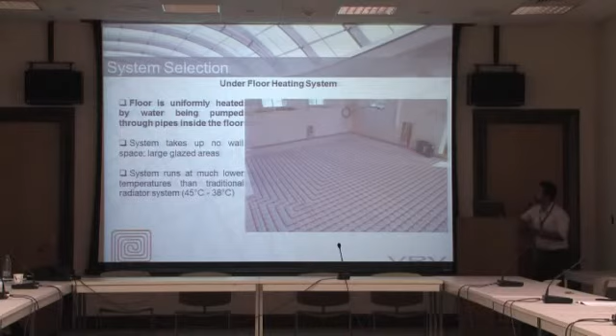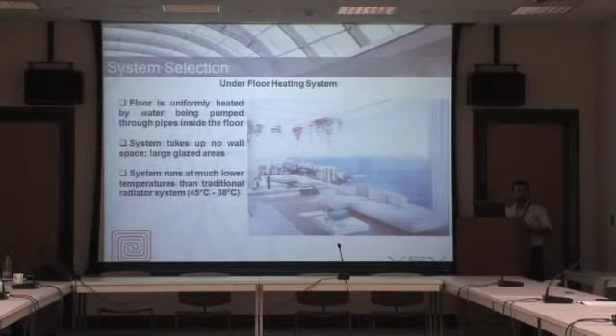The return temperature, or this delta T here, we can use to operate the VRV for cooling or heating as a heat pump. This is what we're going to discuss. This is a schematic configuration. As you see, each tenant has a VRV and an underfloor heating system. This is the water loop we're going to use. We're connecting it to a cooling tower and a boiler.